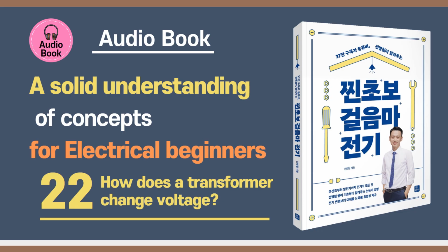Smart. So that explains why transformers can be so heavy, right? All that copper and iron. Definitely, they are dense, but the structure itself is fundamentally simple. Coils, core, insulation. And you mentioned larger ones need cooling. Oh yes. Smaller ones might just be air-cooled, but the big ones you see in substations generate significant heat. They're often filled with a special mineral oil. Oil. Inside a transformer. Yep. It serves two purposes. It's a great electrical insulator for the high voltages inside, and it circulates to carry heat away from the coils and core to the outside, often through cooling fins or radiators you see on the tank. So the oil cools and insulates. Exactly. It keeps things from overheating and failing.